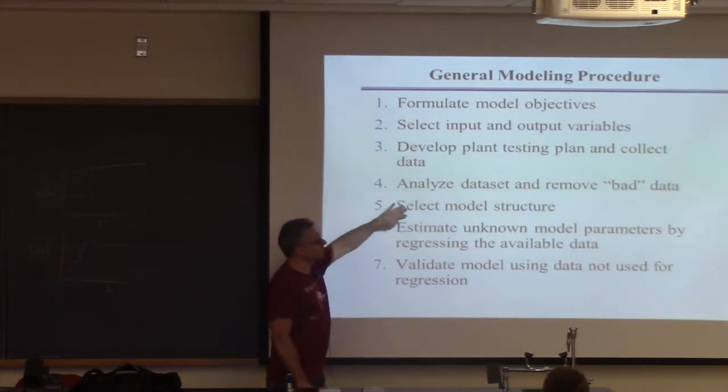Once you have the data, then you have to do something called model structure selection. So let's say you looked at this model here. You're trying to say, what kind of model might work here? Well, the first thing you should conclude is the system looks like it has a time delay, because I changed the input here, and it didn't change for 20 minutes or whatever it might be. Then you're like, oh, system oscillated. It's got to be at least second order, because no first order system can do that. So I would try second order plus time delay.